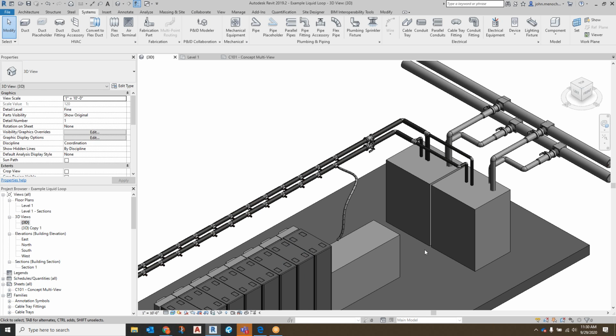I don't care so much that the CDUs are sized at 100 or 500. I care more how I match the CDUs to what my projected total load will be. So I don't have to have a number, this many kW. I have to think in terms of how many CDUs I'll be putting in there, and what is my redundancy - do they all operate at the same time? So the pipe size and piping configuration is kind of less important, on an as-needed basis.